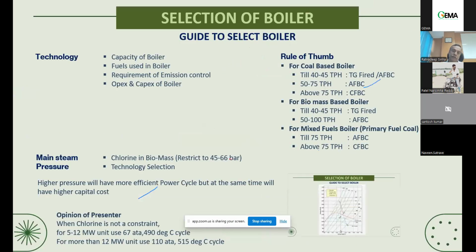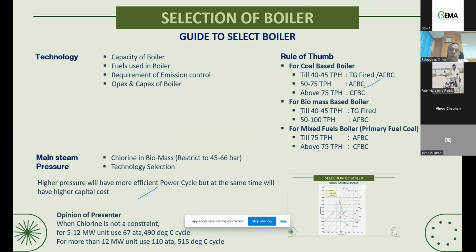As we go for a higher pressure and higher temperature range of a steam turbine, your power cycle will be more efficient. But you cannot increase to infinity. So obviously there are certain considerations. So obviously the technology selection is based on, as I told you, the capacity of the boiler, fuel used in the boiler, requirement of emission control, and Opex and Capex of the boiler. And then what is the rule of thumb for selection of a boiler? Every time you cannot do a calculation. So the rule of thumb is if you are between 40 to 45 TPH, basically you can go for TG fired or AFBC.